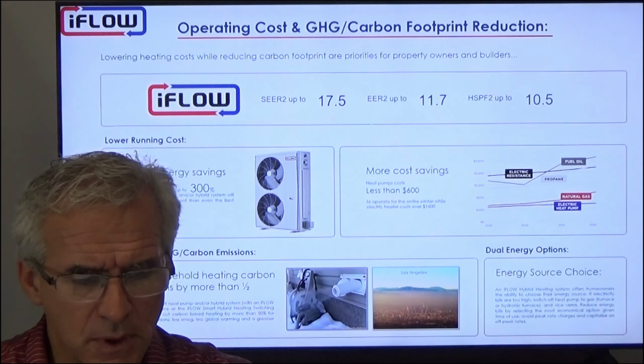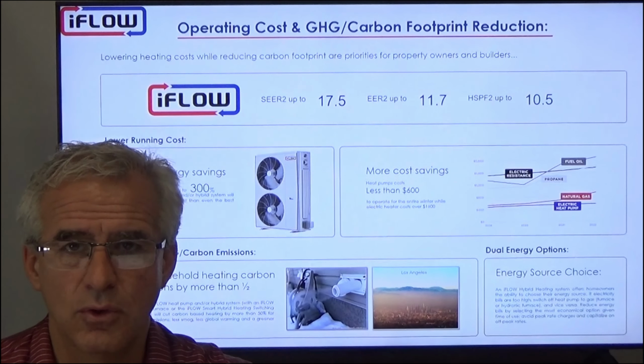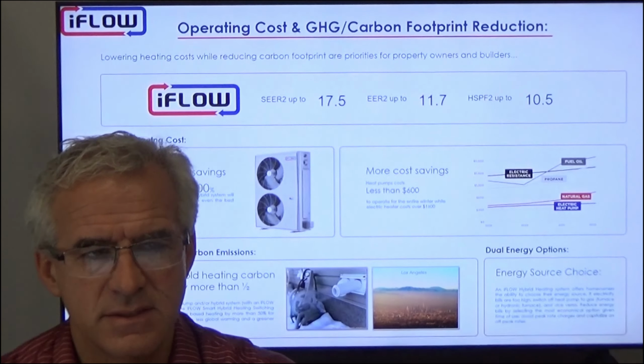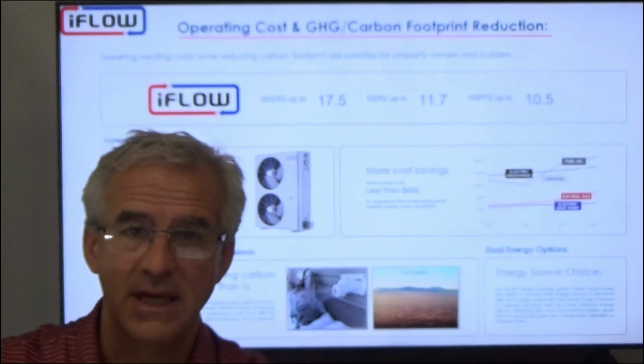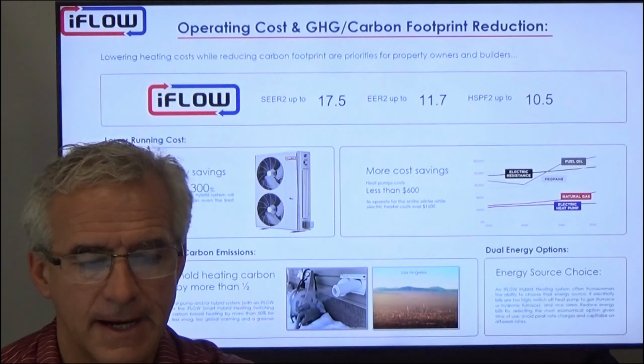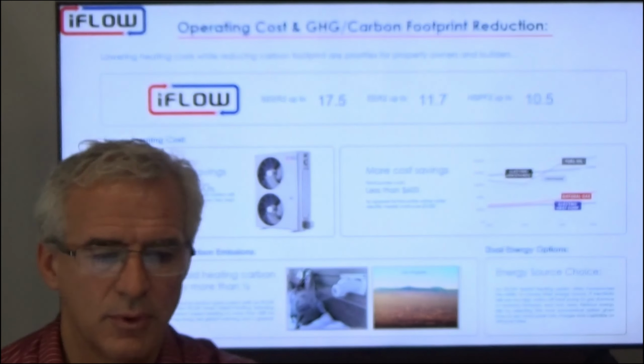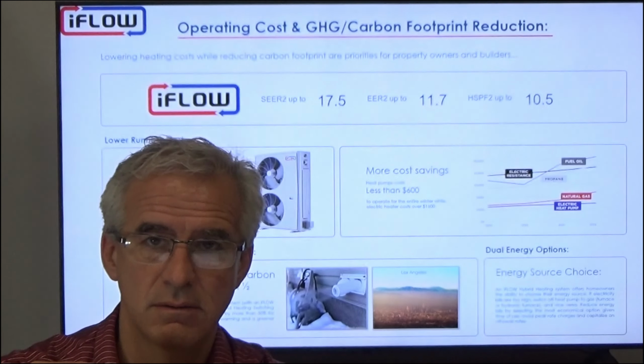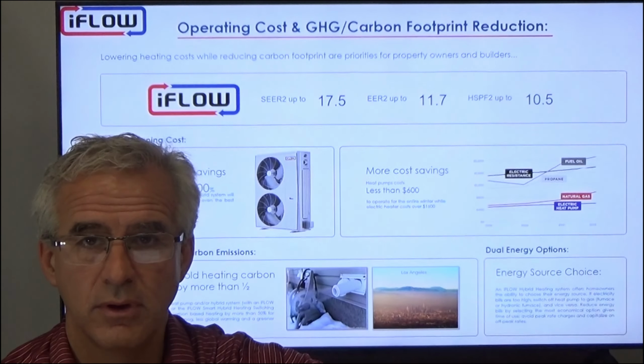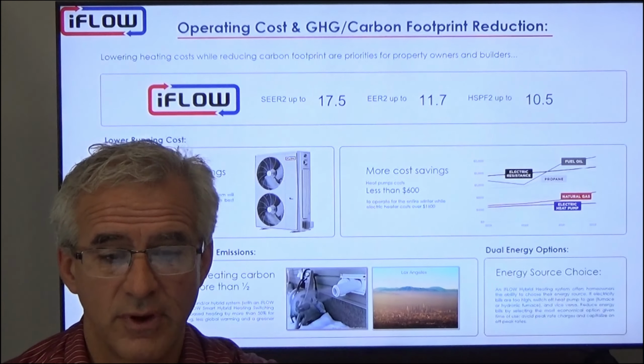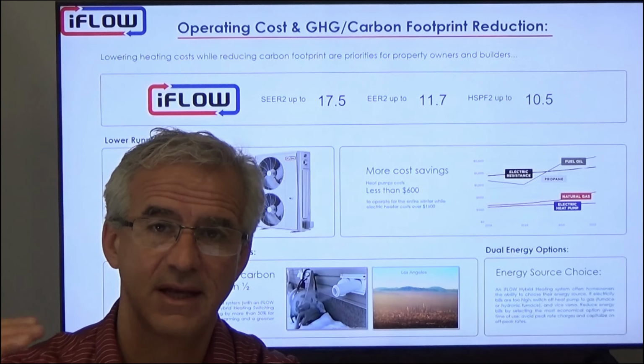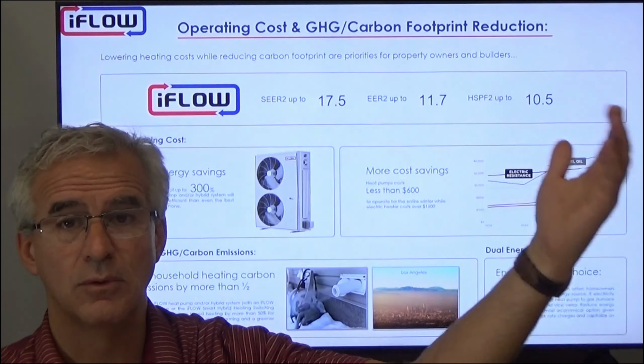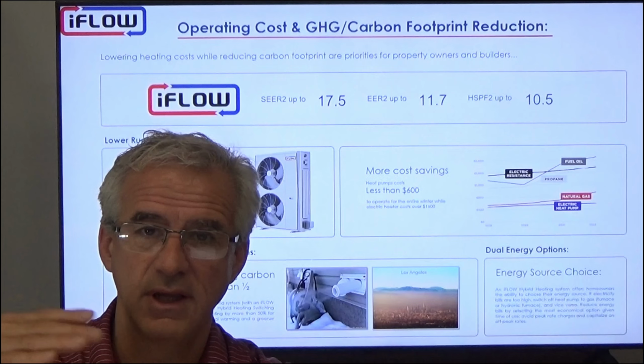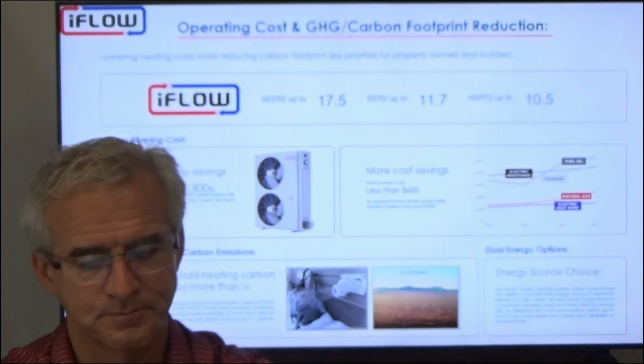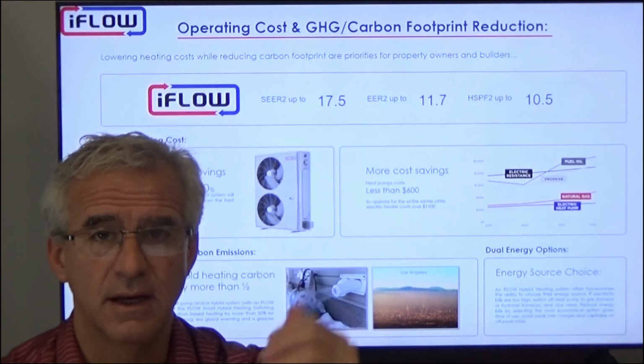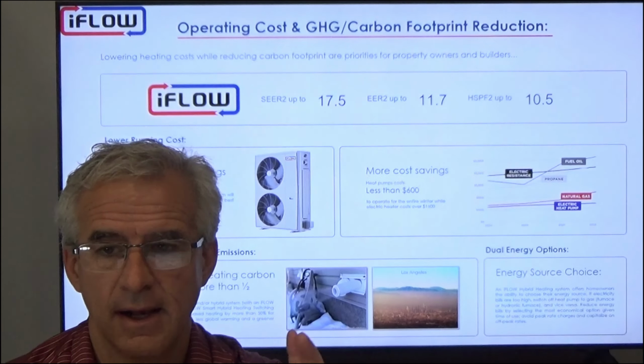In terms of heat pumps, we measure those in what we call COPs, or coefficients of performance. That is a relative number that looks at the energy input and compares it to the energy output and gives you a number. So for example, for every kilowatt in, we get a certain kilowatt out of the heat pump. If we have a COP of 3, for example, what that means is for every kilowatt input, we have 3 kilowatts of output. If we have a COP of 2, we have 1 kilowatt input and we have 2 kilowatts output. So they're very efficient, again up to 300% more efficient than a typical system.